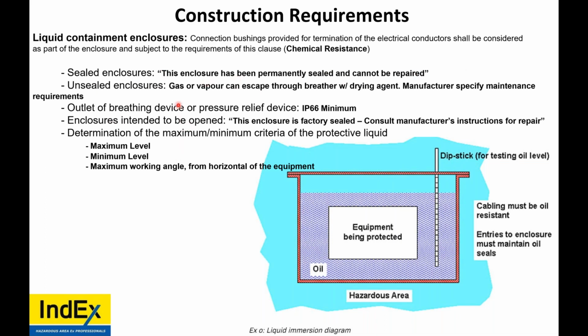Unsealed enclosures will have gas or vapors that can escape through a breather. So if you have a breather at the top here, we'll have a breather with a drying agent. The manufacturer shall specify the maintenance requirements. Outlets or breather devices must have a minimum of IP66.